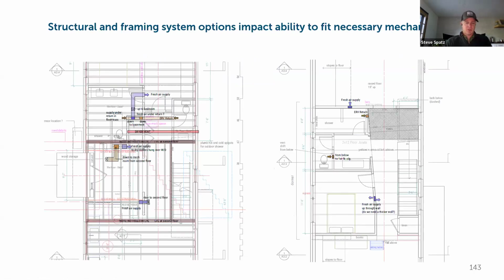And in an ideal world, those things would be identified on the plans. You know, if it's not going to be showing up on the plans drawn up by an architect or designer, then whomever is going to be installing the system should be able to have a chance to look at those drawings and to identify where the equipment's going to need to be, because that may have changes required on structure or other considerations to be made, because you don't want to have a 5-ply microlam right between where the ERV needs to go and where the main plenum line, the trunk line coming out of that, needs to go, with that right in the way. So good design is critical here. We're not just talking about fitting it into the building, but good duct design and following good duct design principles for pressure.